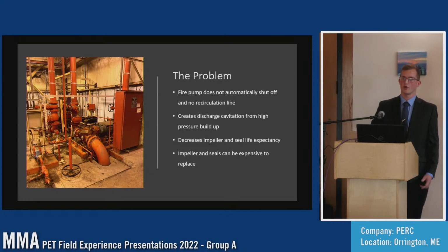This is a big problem because this could not only lead to pump failure, but you would eventually have cavitation bad enough in the pump where you'd have to replace the impeller and seals, which actually the seals are replaced at least once, sometimes 2 or 3 times a year. This repeatedness can cost quite a bit for the plant, and I was just trying to find a way to minimize the amount of cavitation time that the pump was experiencing.